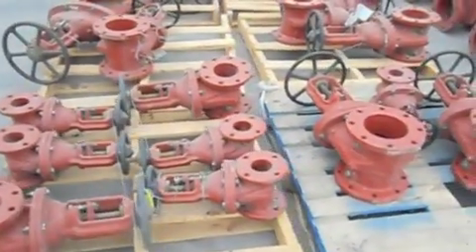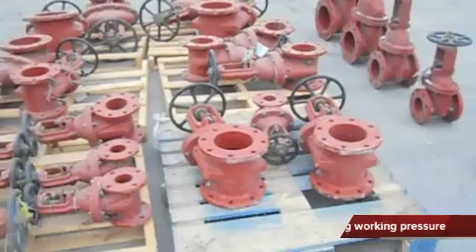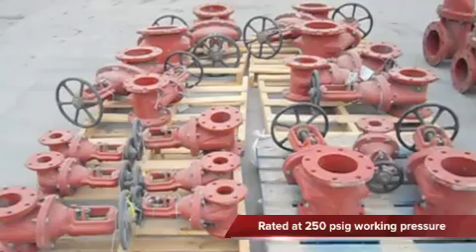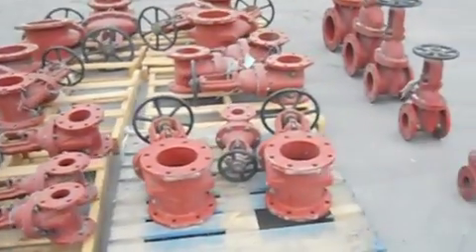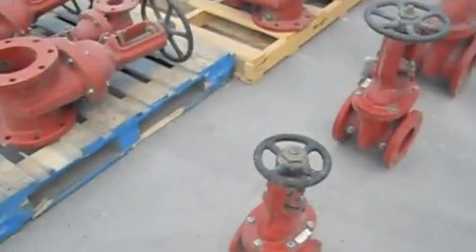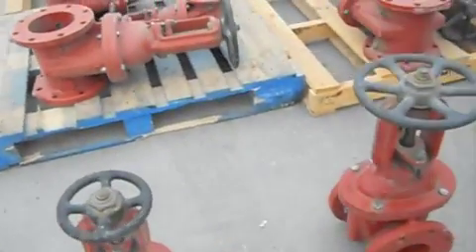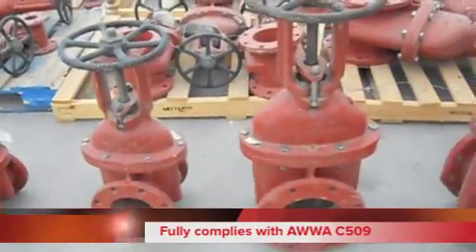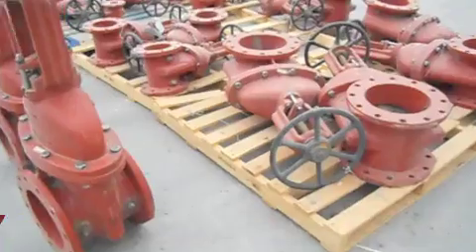Optimized design for consistent performance and long-lasting corrosion resistance, the Mueller valves are rated at 250 PSIG working pressure, 25% higher than stipulated by the AWWA standard, and hydrostatically shell-tested at 500 PSIG. The 2360 Series fully complies with AWWA C509.